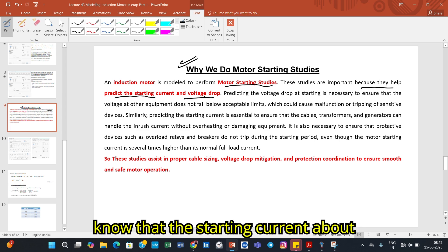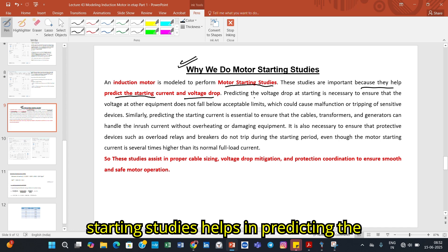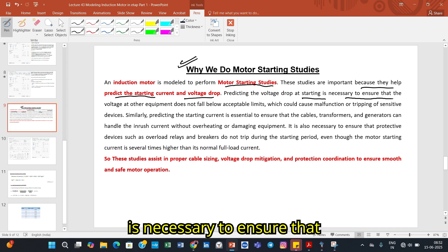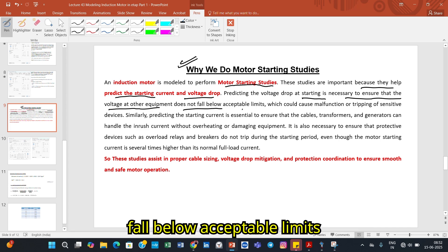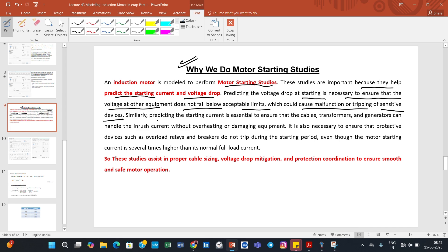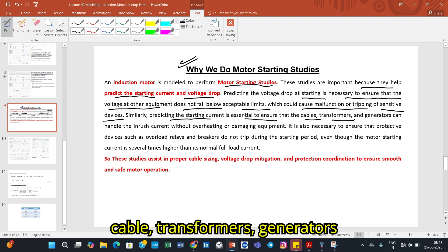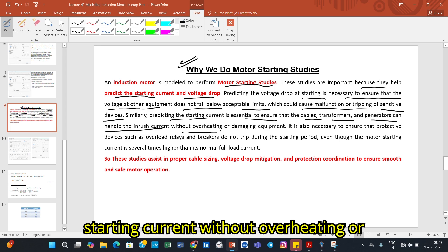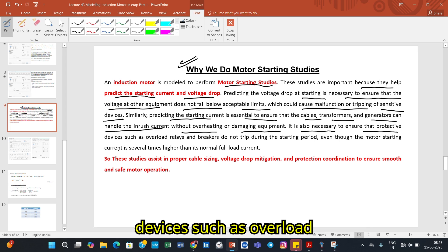We all know that the starting current of an induction motor is very high. Motor starting studies help in predicting the starting current and voltage drop. Predicting the voltage drop at starting is necessary to ensure that voltage at other equipment does not fall below acceptable limits, which would cause malfunctioning or tripping of sensitive devices. Similarly, predicting the starting current is essential to ensure that cables, transformers, and generators can handle the inrush current without overheating or damage.